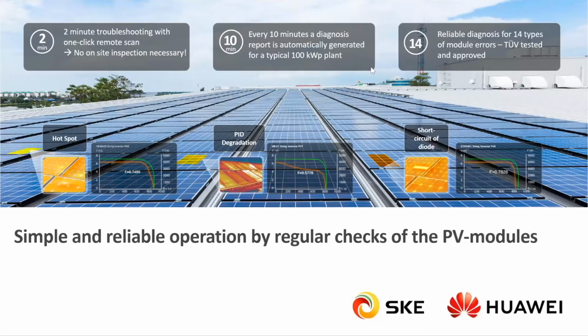A feature that our inverters have is the IV curve function, which allows us to find up to 14 different types of module errors. And this was tested by TUV. Some of the errors which can be found on the DC side are hotspots, potential induced degradation, and short circuit of diodes. The scan is extremely quick, and you can find out from a full report the health of the DC side of your PV system.